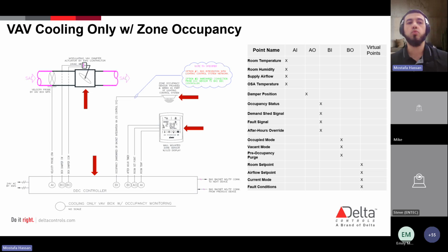closed. Now, how do we manage the cooling or heating in this space? If this VAV had a heating coil, or the air handling unit is pushing heated conditioned air through the space, well, the controller is going to compare the set point with the space temperature, right? So if it needs cooling, then it's going to modulate, and if it needs heating, it's also going to modulate and allow the specific air to flow through until the desired temperature is reached.